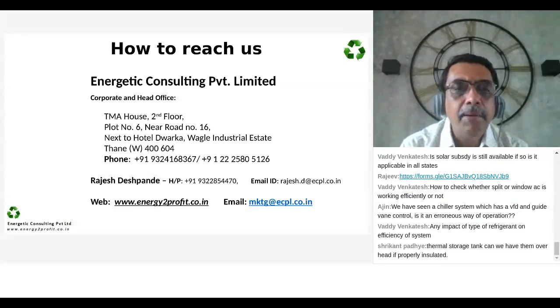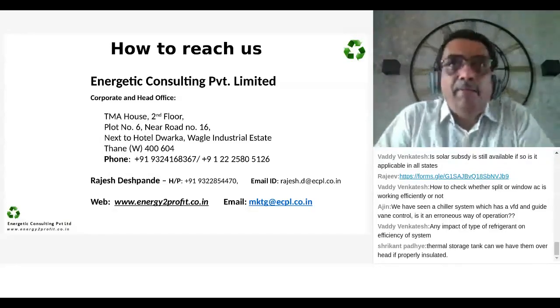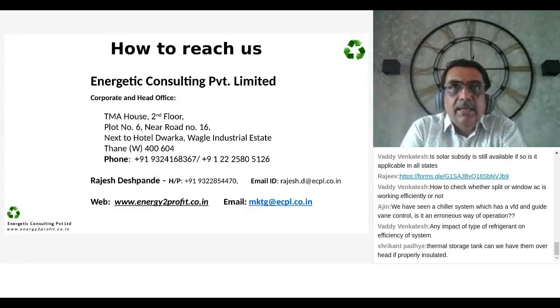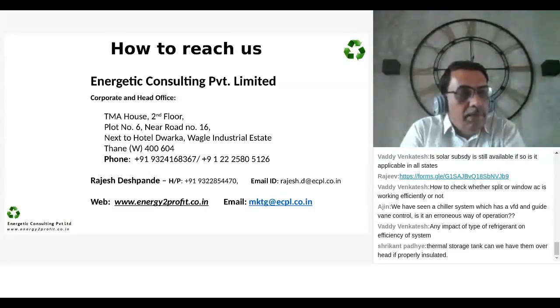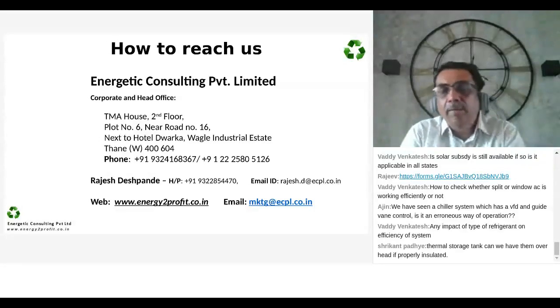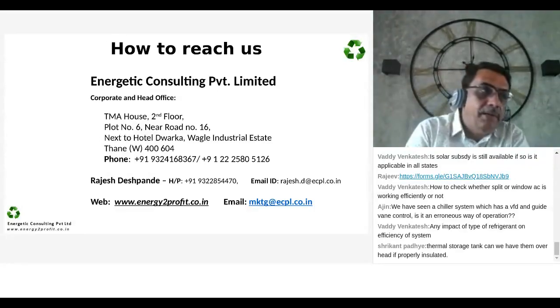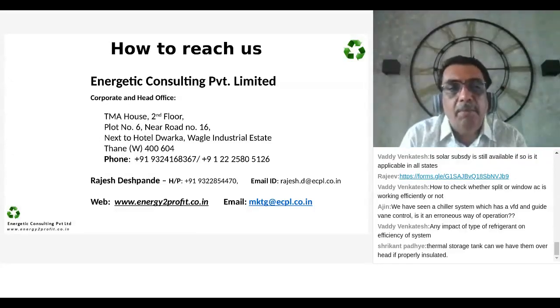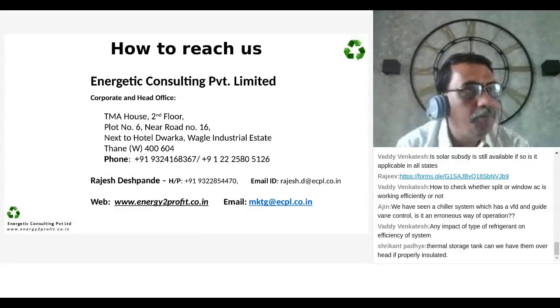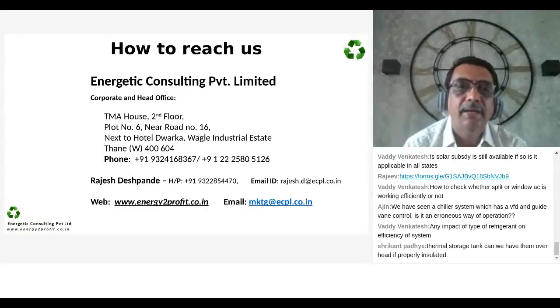On the impact of the type of refrigerant on the efficiency of the system, the answer theoretically is yes. From refrigerant to refrigerant, there is an energy efficiency difference. If we go to, let's say, negative temperatures, ammonia is a better refrigerant. If we go to higher temperatures, maybe some of the hydrocarbons are better, but the impact is not very significant. It could be 2 to 4%. You don't expect 20% kinds of impact because of the refrigerant change.